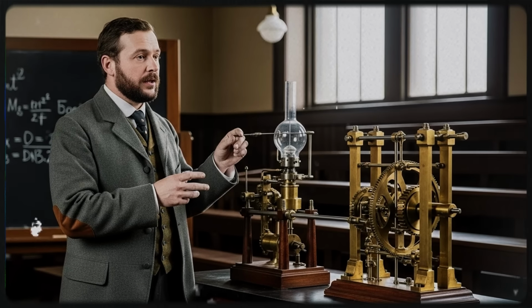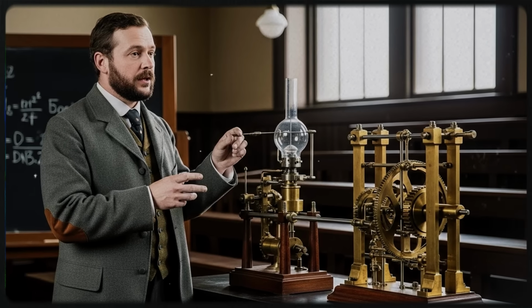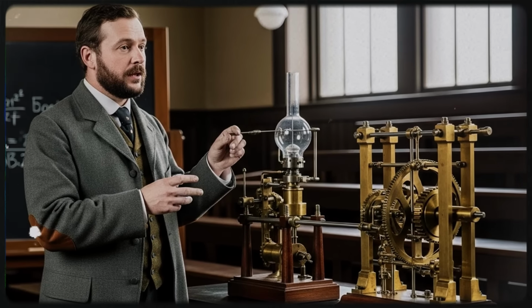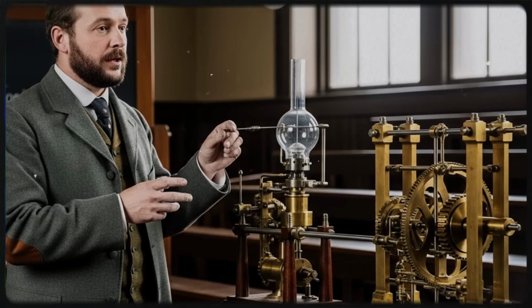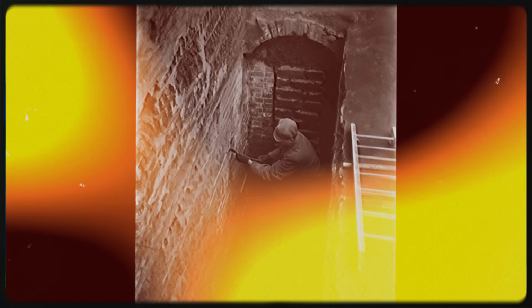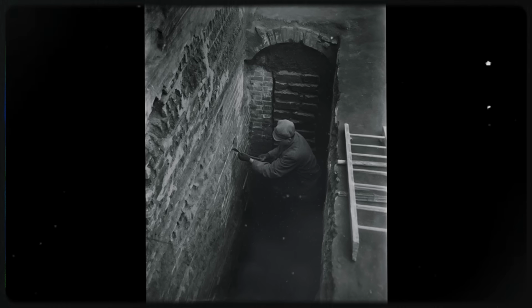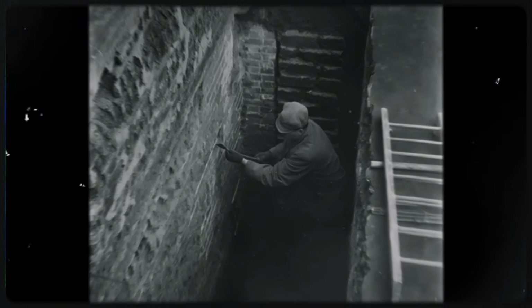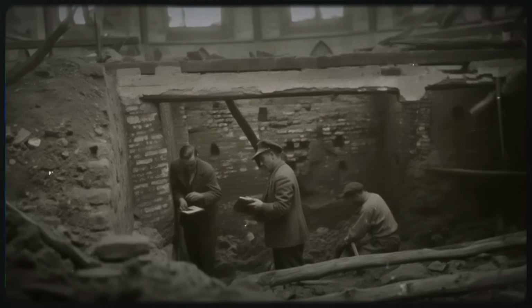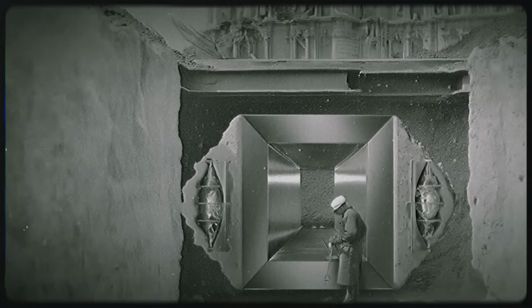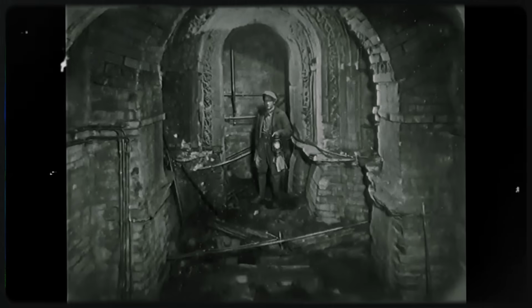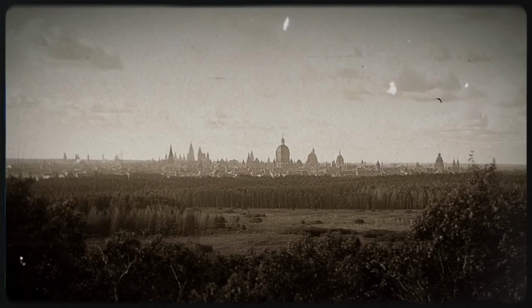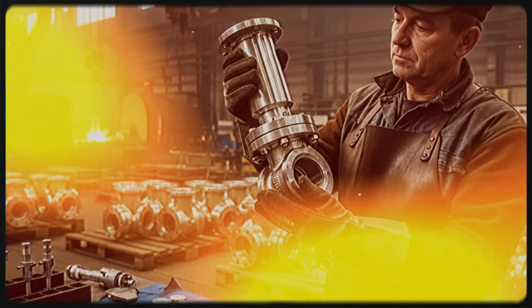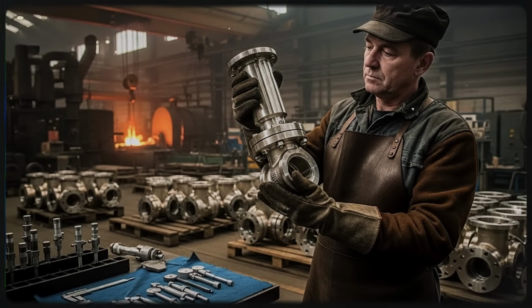Typical implementation used the principle of the centrifugal governor adapted for hydraulic control. A centrifugal governor mounted on the turbine shaft detected changes in speed. Movement of the governor's spheres controlled a pilot valve in the hydraulic system. The pilot valve directed pressurized oil to a large piston that opened or closed the turbine's water gates. The leverage system created amplification. A small movement of the governor caused a large movement of the gates.